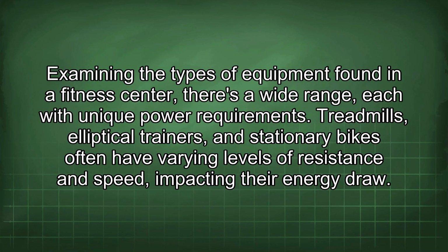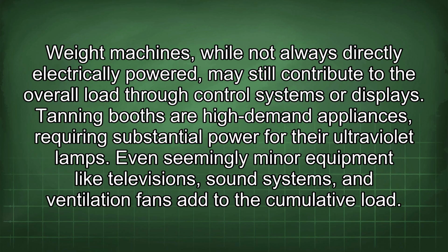Examining the types of equipment found in a fitness center, there's a wide range, each with unique power requirements. Treadmills, elliptical trainers, and stationary bikes often have varying levels of resistance and speed, impacting their energy draw. Weight machines, while not always directly electrically powered, may still contribute to the overall load through control systems or displays. Tanning booths are high-demand appliances requiring substantial power for their ultraviolet lamps. Even seemingly minor equipment like televisions, sound systems, and ventilation fans add to the cumulative load.